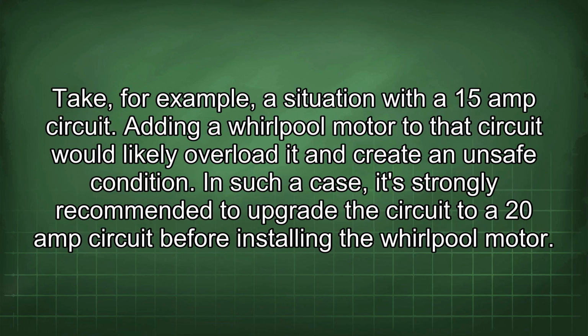Take, for example, a situation with a 15-amp circuit. Adding a whirlpool motor to the circuit would likely overload it and create an unsafe condition. In such a case, it's strongly recommended to upgrade the circuit to a 20-amp circuit before installing the whirlpool motor.